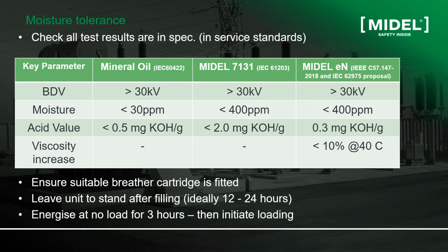And finally, once you finish this retrofill, you can mount a new breathing cartridge to make sure the transformer or the liquid is not wet. You can leave the transformer to stand for 24 hours or 12 hours before connecting to full load. Usually before connecting to full load, we ask to connect for 3 hours at no load. This will aid us in heating the liquid and removing any air bubbles from the transformer to the outside.